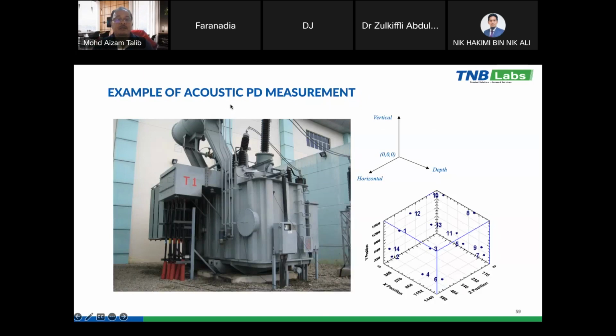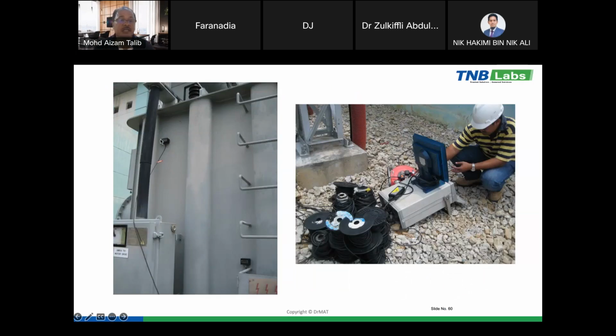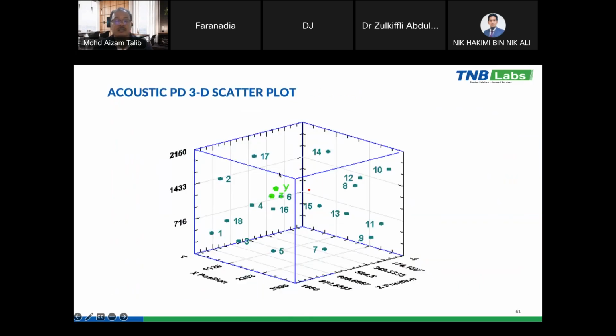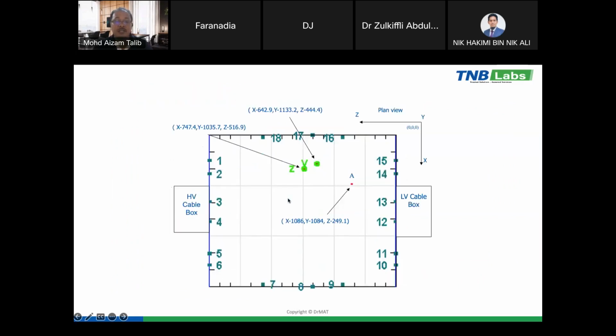Okay, this is an example of the acoustic PD measurements. Here we put sensors around the transformer, and we measure exactly the length of the transformer, X, Y, Z, and then we need to measure exactly the location of each sensor. This is the acoustic sensor put on the transformer tank, and then finally we are able to pinpoint the location of the PD. This is from the top view.